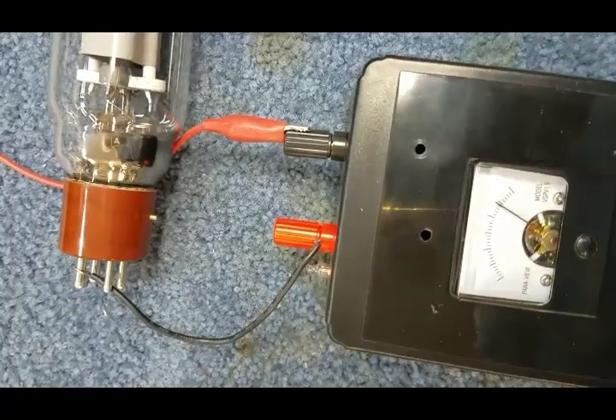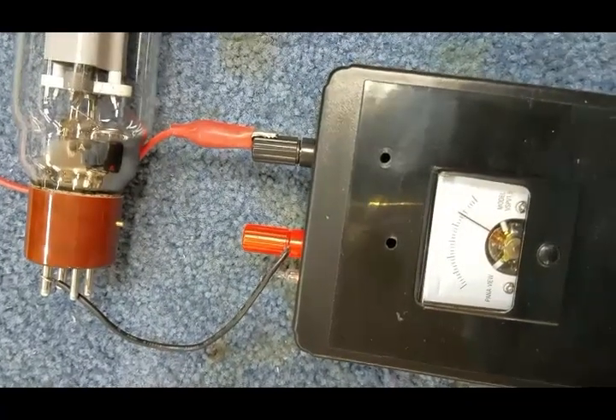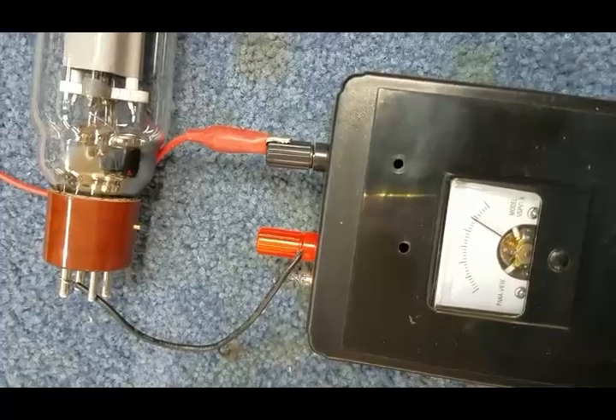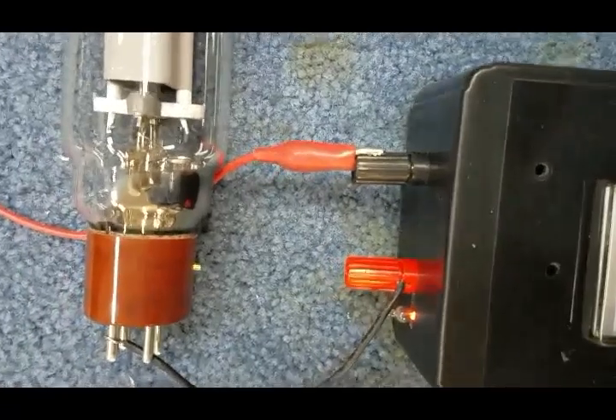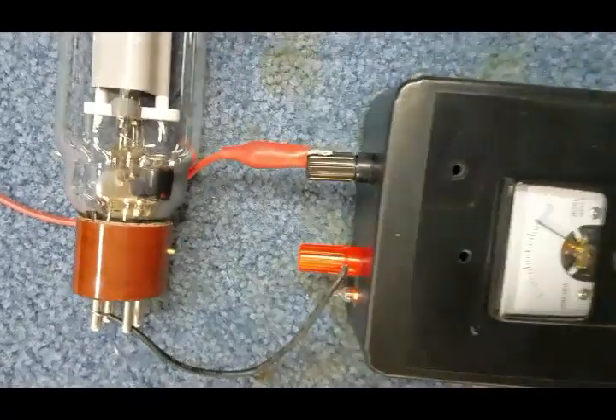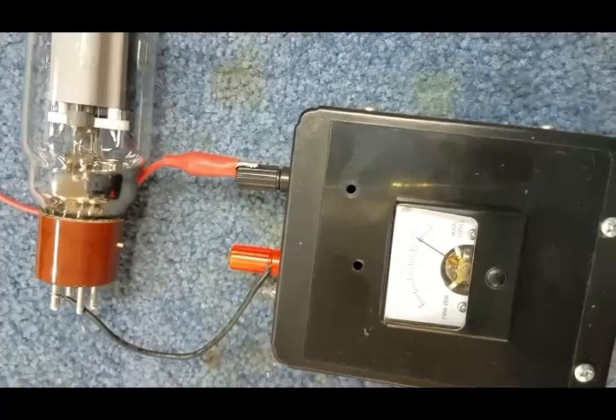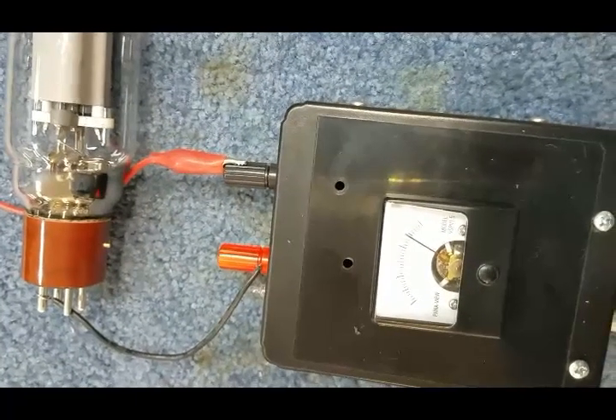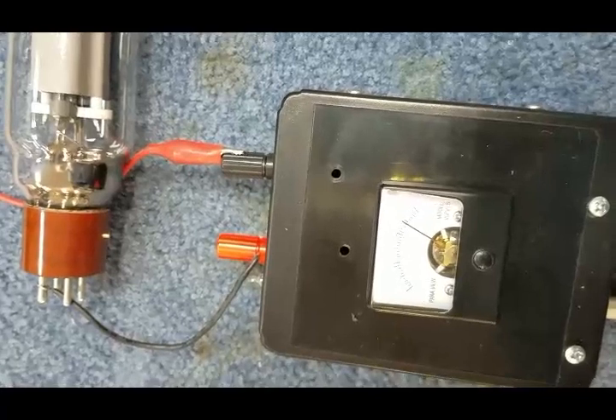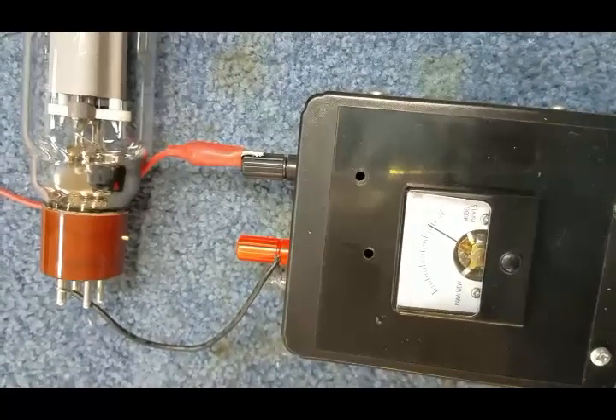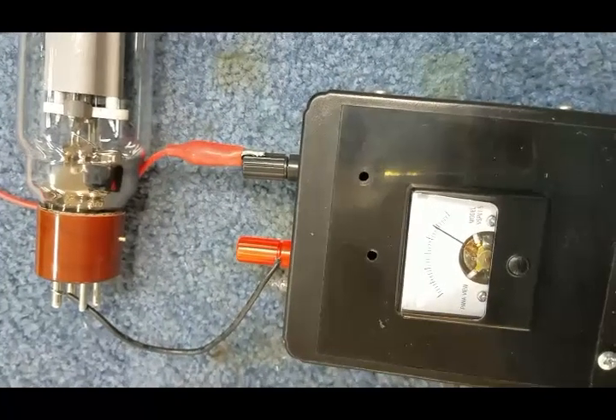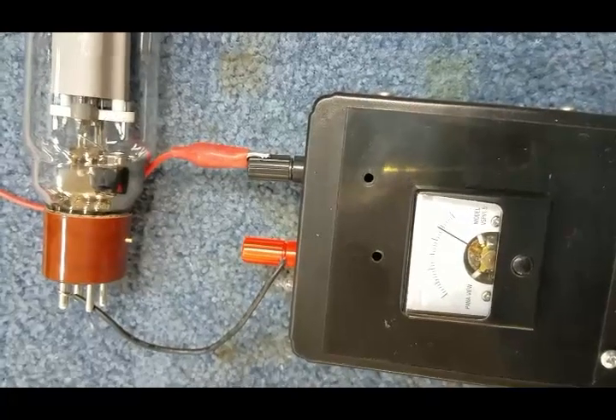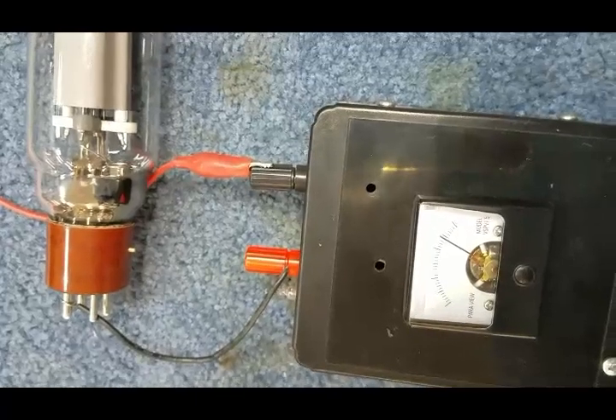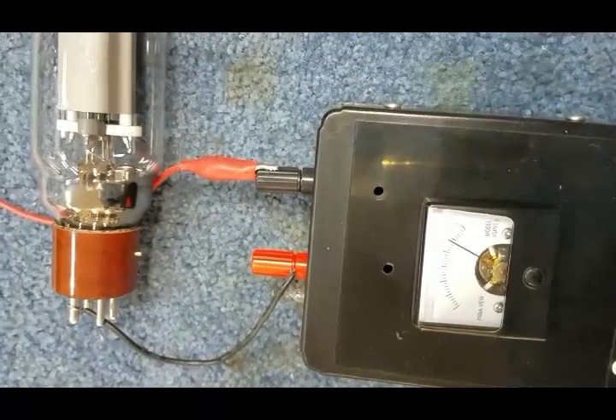Let's see, that's 5,000, 7,500, this is 10,000 volts. At 10,000 volts, the tube is just starting to show, just starting to load the meter -- you can see it fluctuate a little bit. So it's just barely starting to draw current at 12.5 -- let's see, are we at 12,500?